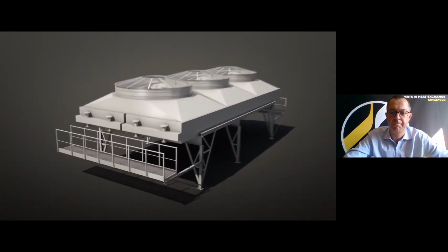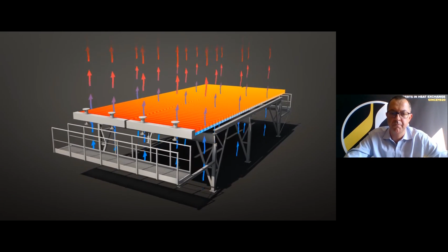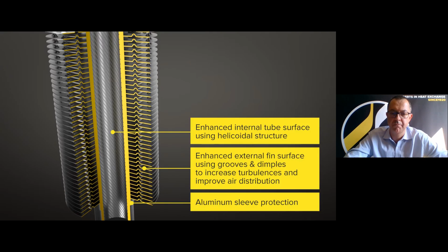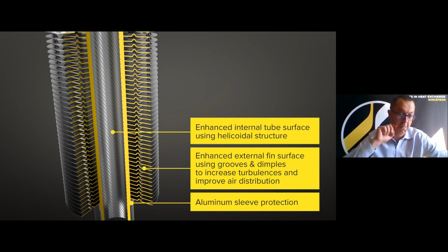In standard air-fin coolers, a fan forces or induces ambient air through the tube bundle. The tubes contain the process medium, which is cooled by ambient air. But what makes DIESTA special? DIESTA has three key characteristics that lead to major benefits. The tubes have a helicoidal structure on the inside, which enhances the internal tube surface. On the air side, grooves and dimples enlarge the surface area of the aluminum fins, improving air turbulence and heat transfer. An aluminum sleeve protects the carbon steel core tube from corrosion.